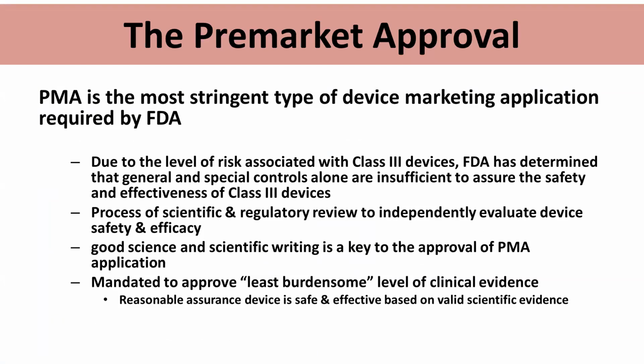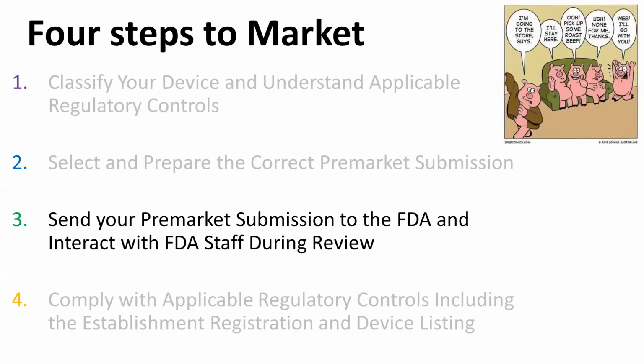So the PMA is the most stringent type of the marketing application. And that's because of the risk associated with class 3 devices. So the FDA wants to make sure that there's good science, that there's good regulatory review, but they are still mandated to be least burdensome with the level of evidence. So you don't have to have necessarily a randomized control study. As you can see, there's significantly more on the outline for the PMA.